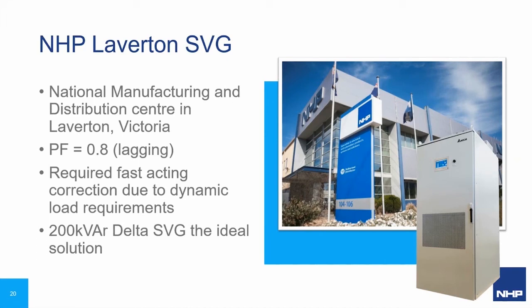So the distribution centre is 12,000 square metres and it develops world-class customised solutions through manufacturing, assembly, servicing, design, engineering and distribution of over 1,500 stock lines. So the facility itself had a power factor of 0.8 lagging on average, and we required an innovative solution to correct power factor, improve the power utilization on site, and greatly reduce our electricity bills.